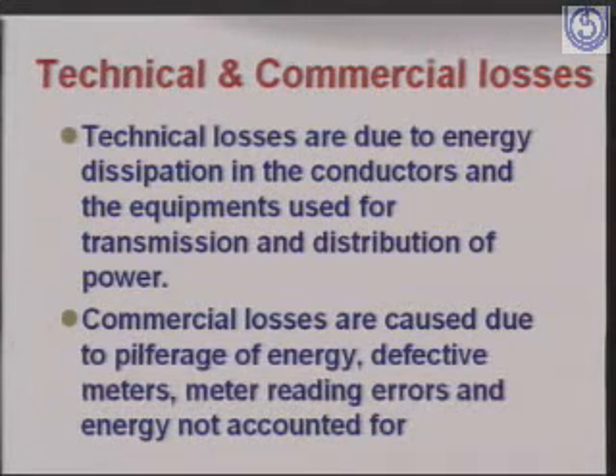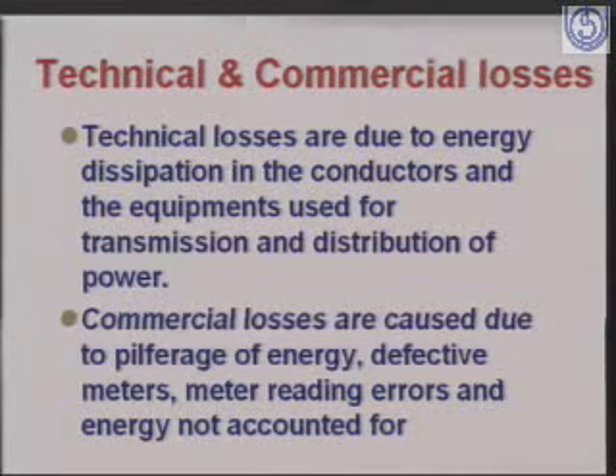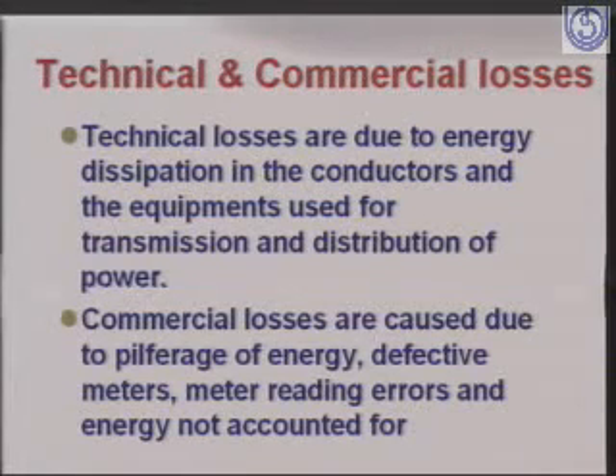There are two losses which take place in any distribution system. First is the technical loss, second is the commercial loss. Technical losses are due to energy dissipation in the conductors and the equipment used for transmission and distribution of power. So whenever current flows, it encounters conductor resistance, and there is a loss to the extent of I square R. Second are the commercial losses, which are caused by pilferage of energy, defective meters, meter reading errors, and energy not accounted for. So basically we have two losses: one is technical losses, which are on account of the system, and second is the commercial loss.